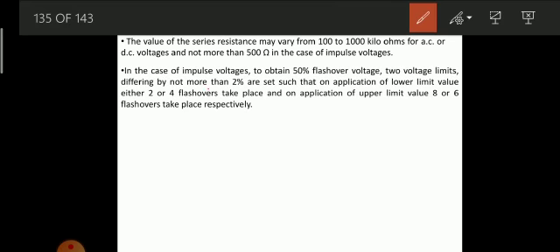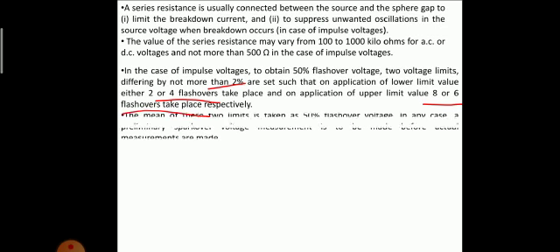So if I consider an example, say 10 kilovolts to 12 kilovolts I have to measure. What we do is, at 10 kilovolts I apply a voltage of 10 kilovolts and check for 2 to 4 flashovers. Then I apply 12 kilovolts and check for 8 to 6 flashovers. Then I take the mean of these two limits, and it is taken as the 50% flashover voltage.